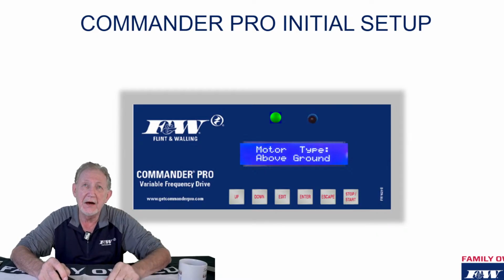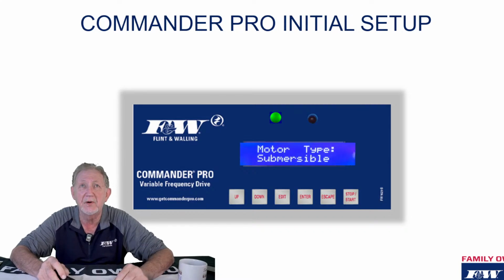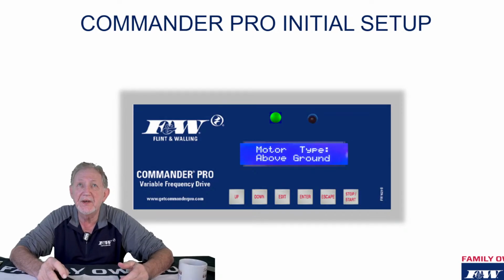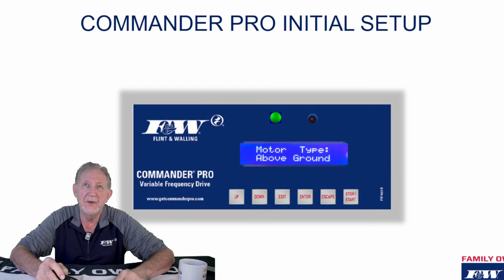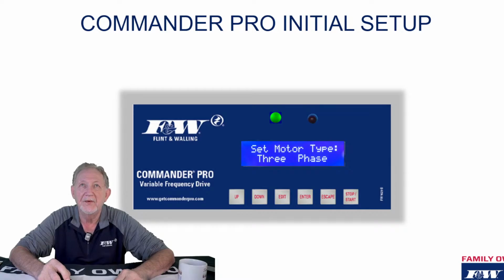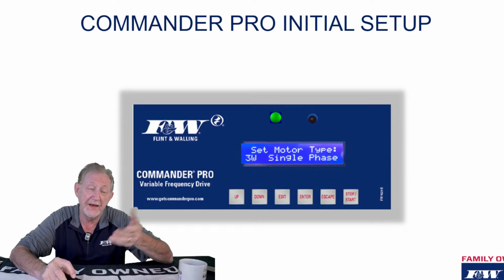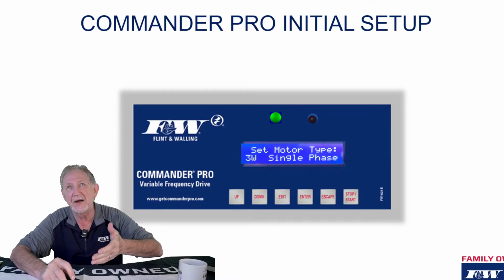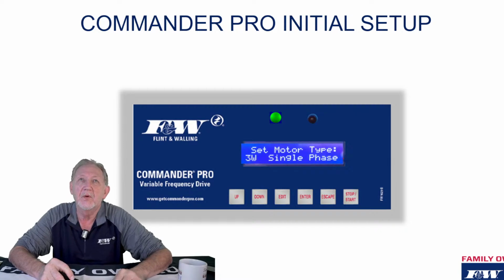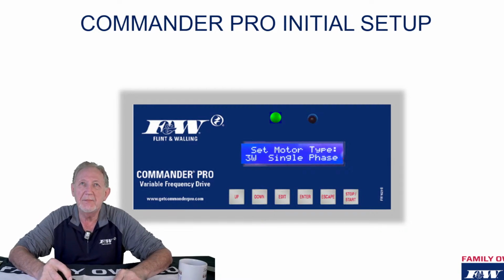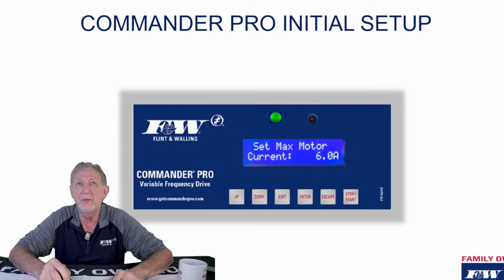And again, you can use your up and down buttons, there you go, or is it an above ground motor like a centrifugal pump motor? So again, you've got submersible, above ground, you make your choice there, and then you would hit enter to make that selection. So let's just run on the premise that we're going to go ahead and select a submersible motor. So then if it's a submersible motor, it's going to ask us, is it a 3-phase motor or is it a single-phase motor? All right, this is not difficult. It's all part of this quick start setup initially. We're going to educate this drive on exactly what type of motor it's going to have to operate. So again, there's your choices between 3-phase or 3-wire single-phase.